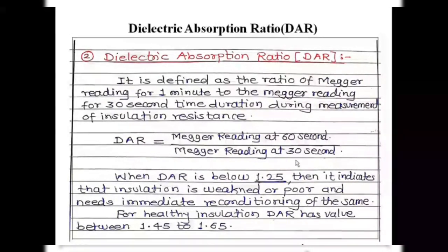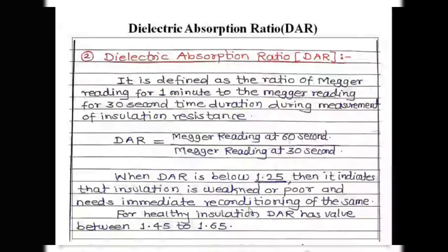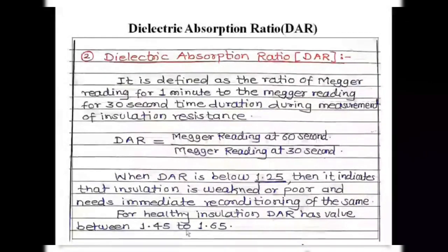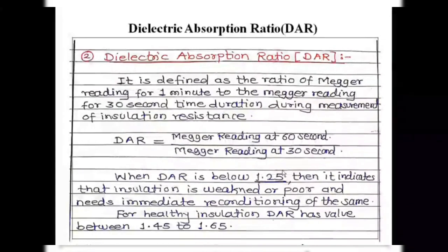DAR is a ratio, so it gives a number. If we get this ratio below 1.25, it indicates the insulation is weakened or poor, has absorbed moisture or impurities, and should be immediately sent for reconditioning. If the DAR falls in the range 1.45 to 1.65, the insulation is in good healthy condition and no reconditioning is needed. If the value is between 1.25 and 1.45, the insulation has deteriorated slowly but immediate action is not required — reconditioning can be done within a certain period of time.